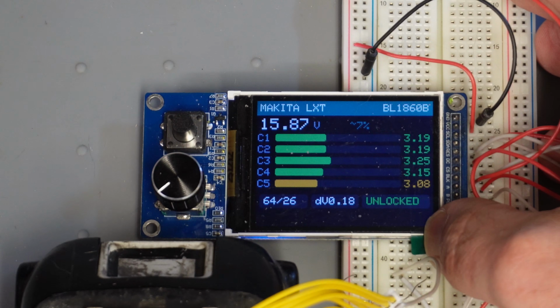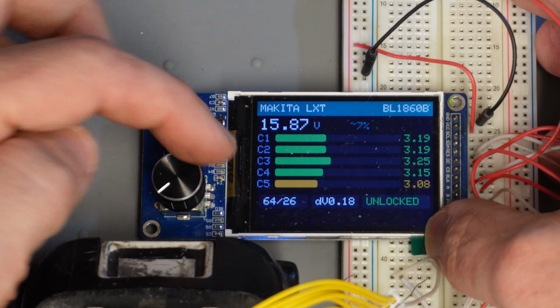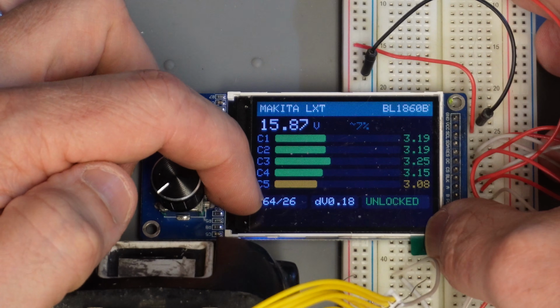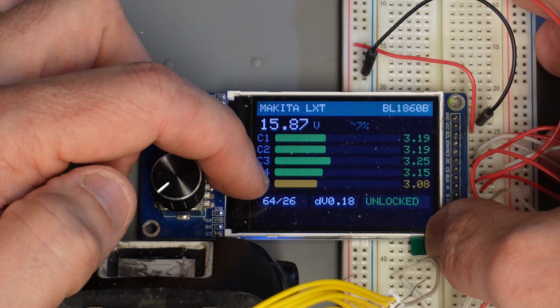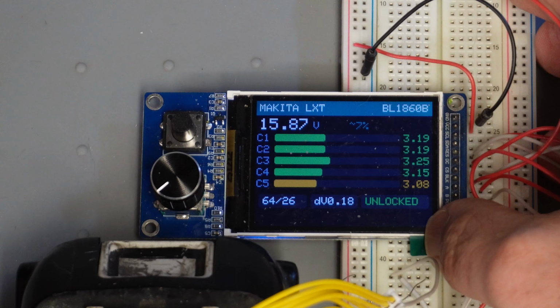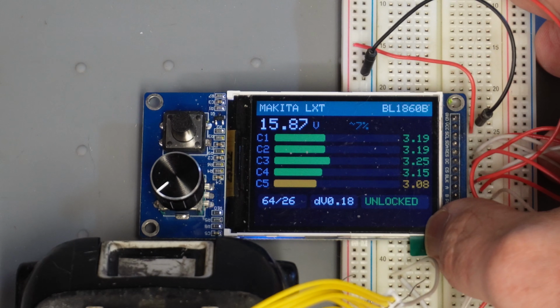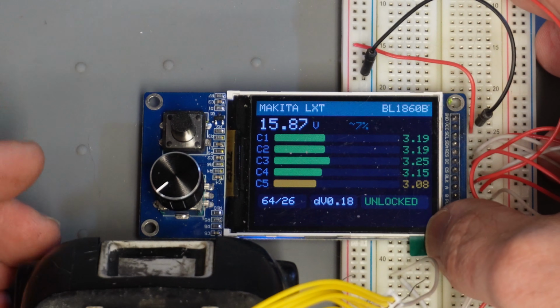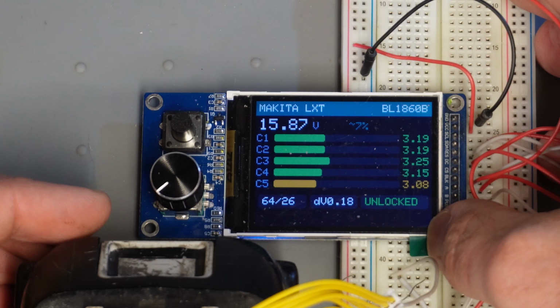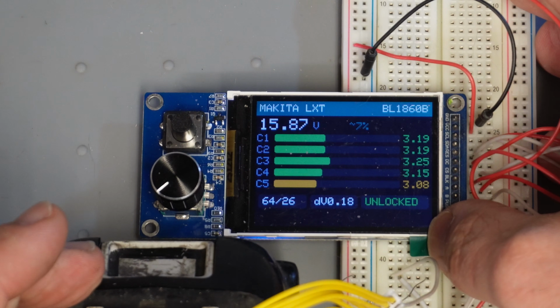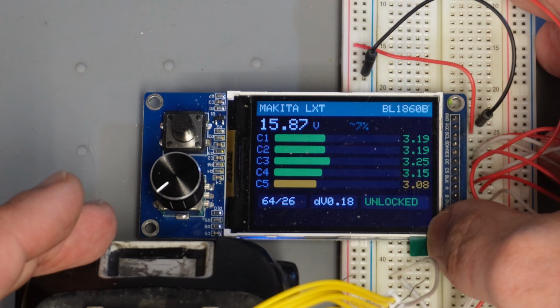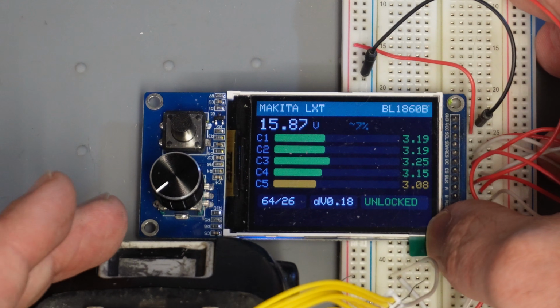But see, 64-26 in terms of the resistance. So I guess in that case, when we have 64, which is so much higher than the nominal, we should have a thermistor that is much lower in resistance than the one we had before that was really high in the range of resistance. That will be a good way to understand if this is an issue with the thermistor again, and whether we can fix it by just changing the thermistor.